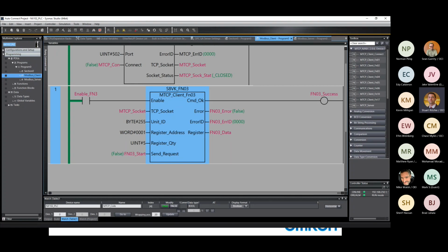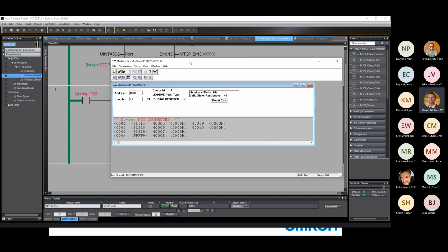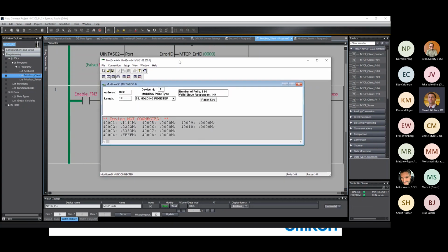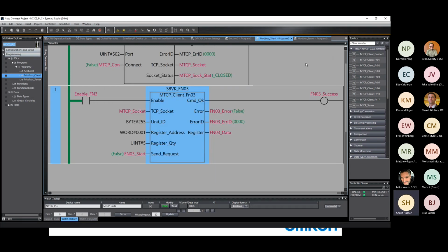Yeah, and you know, it can be a bit cumbersome when you're doing some guesswork with a PLC. What I usually tell people to do with Modbus when you're feeling things out is use a PC-based program like ModScan or MDBus. There are countless free Modbus clients out there, and it's a lot easier to type different registers and scan different ranges and see which function codes are responsive using PC software, and then you can simply replicate that in the PLC once you sort those out. You are right.